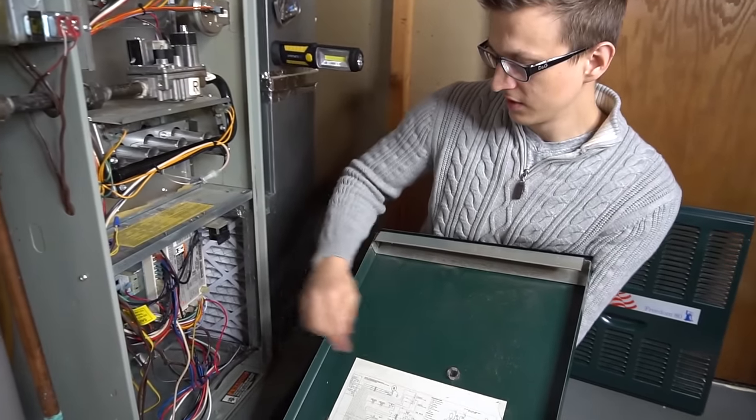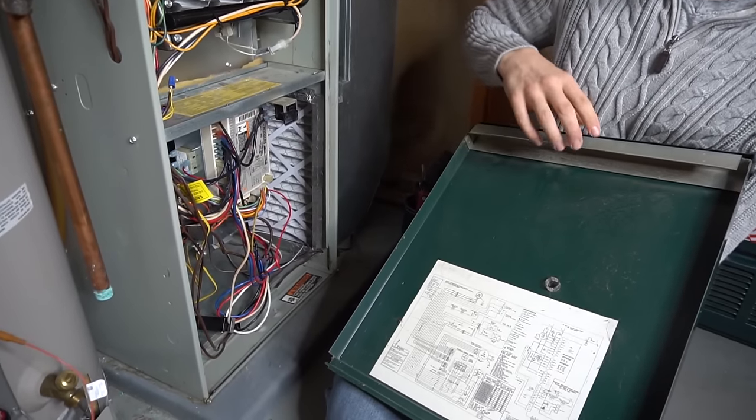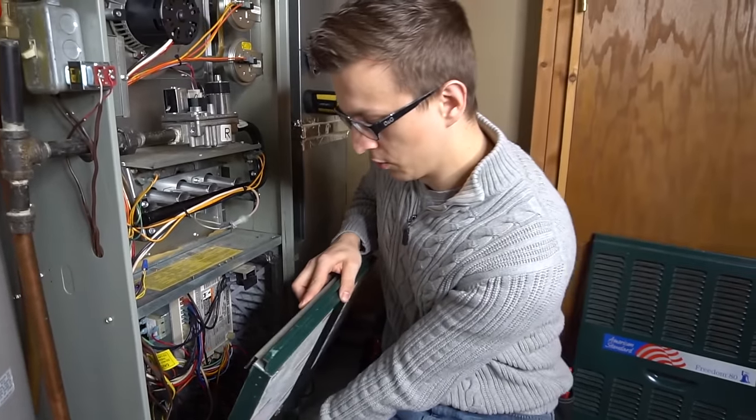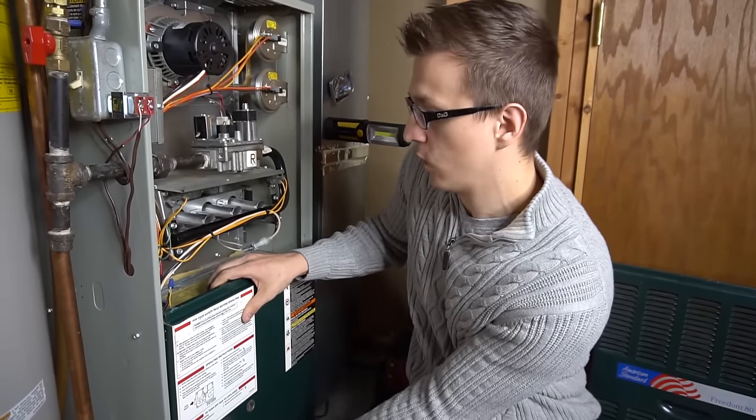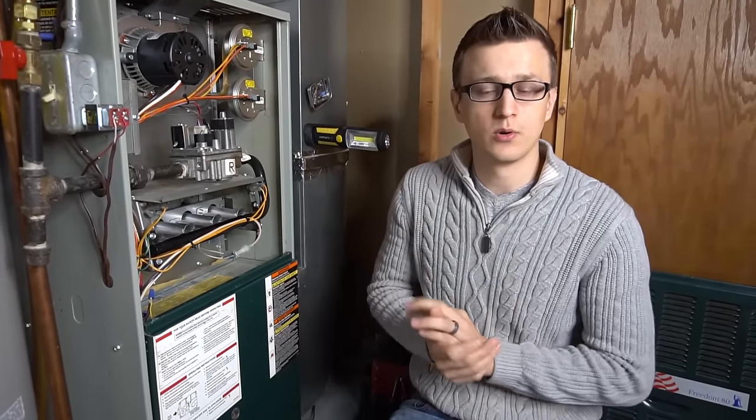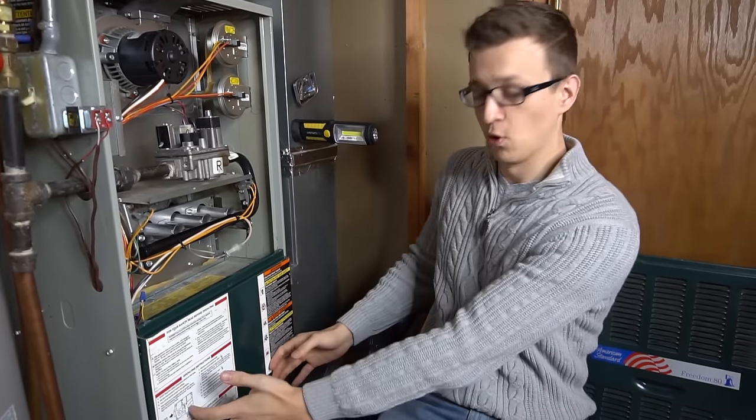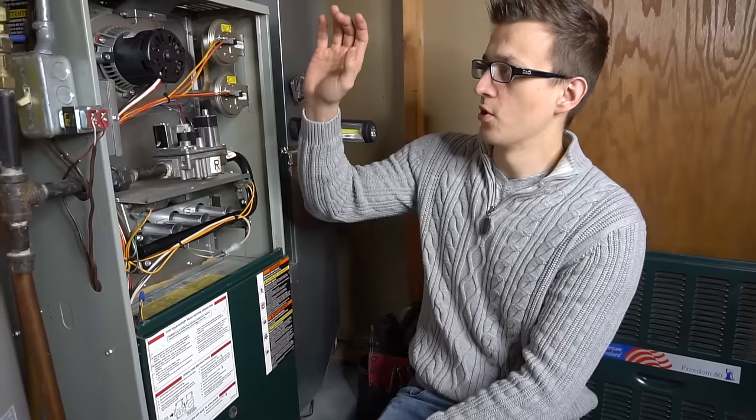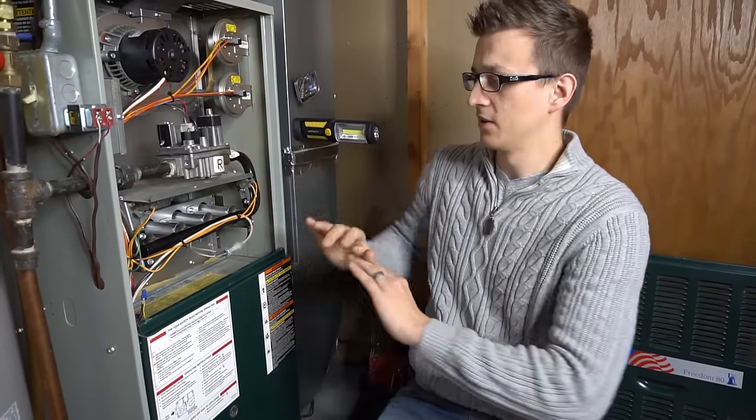You can look at it through the sight glass, or the codes are explained right on the control board itself. Your board will likely be blinking a rollout switch open error code. Typically, your blower motor will be running, your inducer motor will be running, or maybe just the blower motor alone and nothing else is happening.